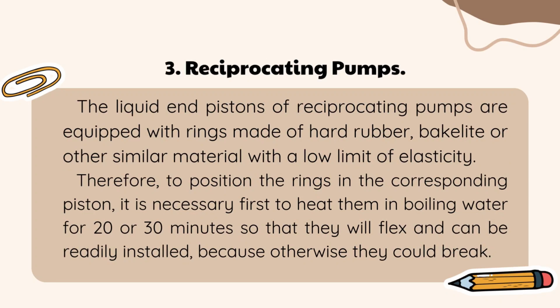3. Reciprocating pumps. The liquid end pistons of reciprocating pumps are equipped with rings made of hard rubber, bakelite or other similar material with a low limit of elasticity. Therefore, to position the rings in the corresponding piston, it is necessary first to heat them in boiling water for 20 or 30 minutes so that they will flex and can be readily installed, because otherwise they could break.